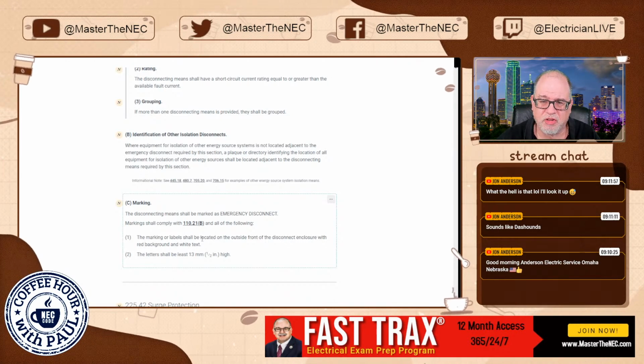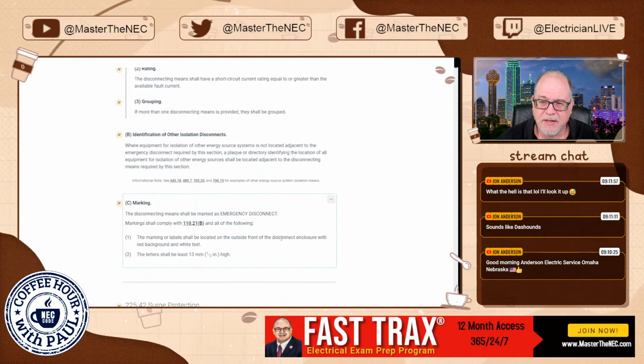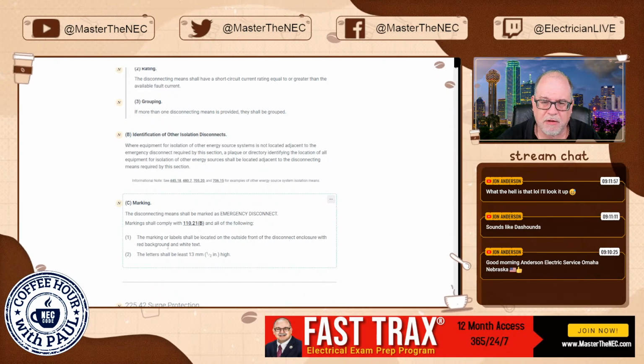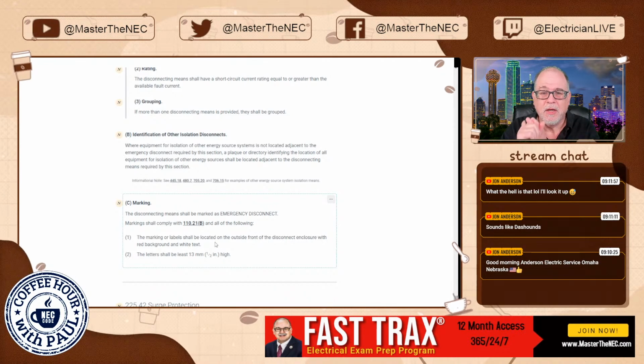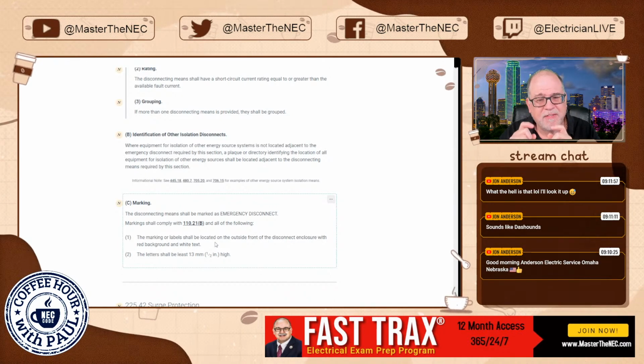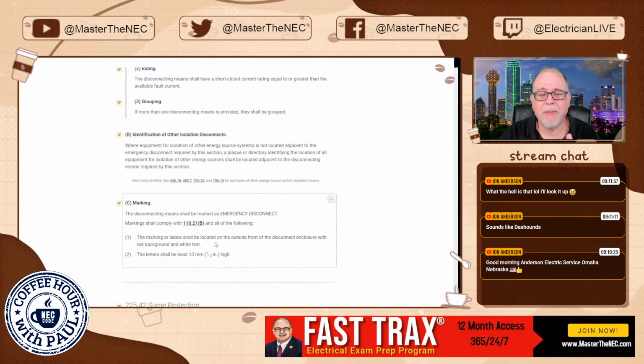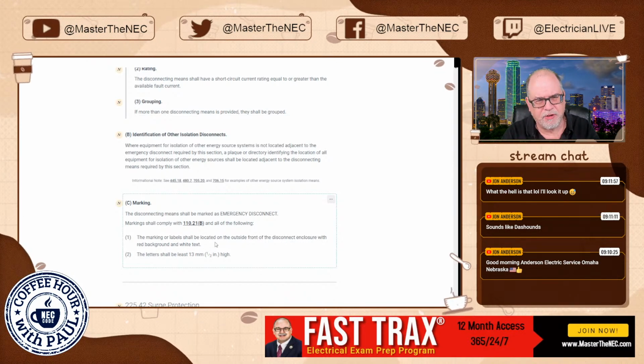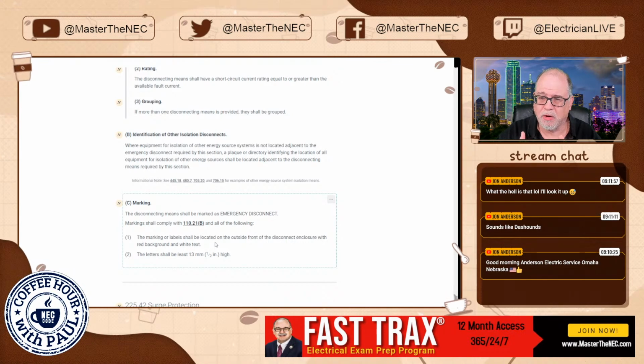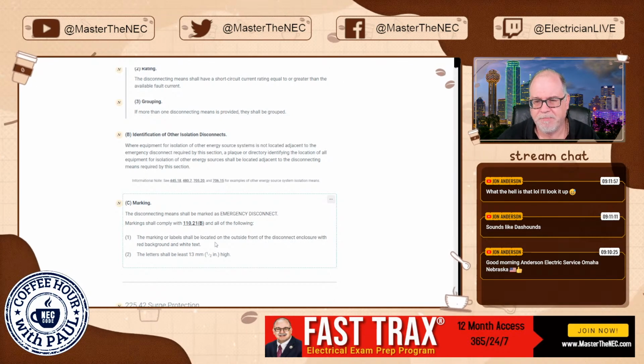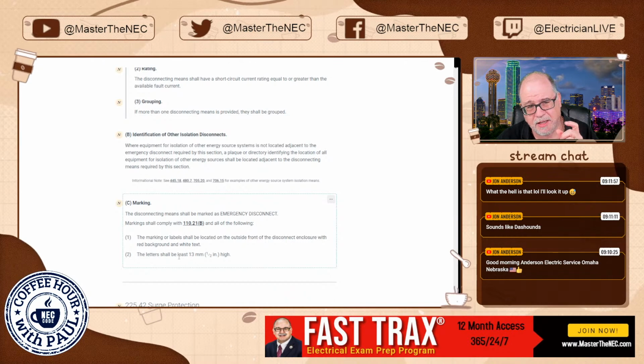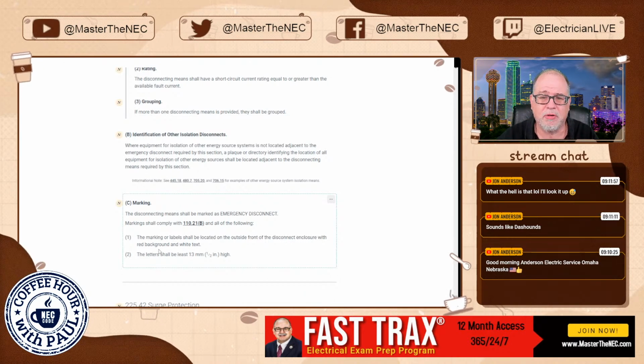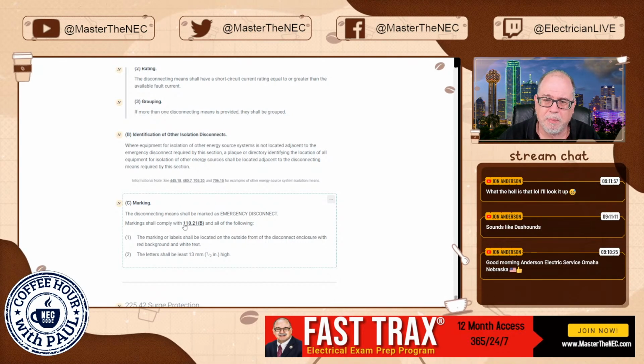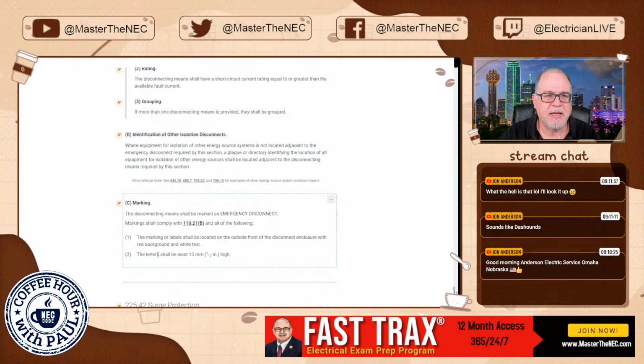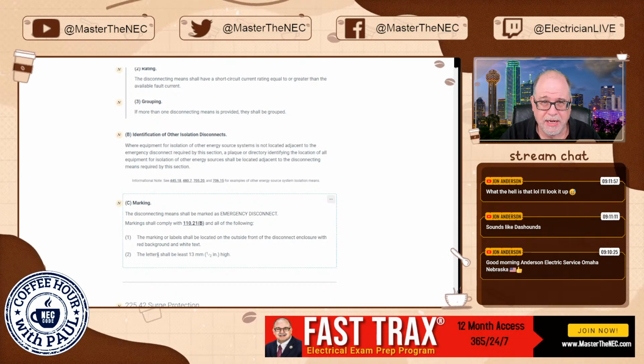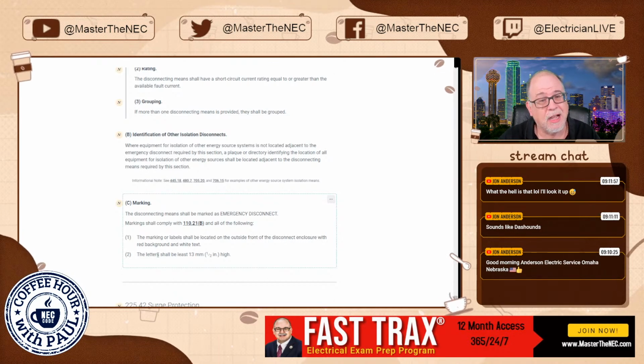It says the marking label shall be located on the outside front of the disconnect enclosure with red background and white text. So the marking is very specific, right? And people have asked through the years, can it be inside of the cover and whatnot? No. It has to be where? On the outside front, all right? And again, it's going to tell you the height of the letters, very specific in these labelings. And also, it goes without saying, they have to comply with 110.21(B), and it means they have to be rated for the environment in which they're located. So no, inkjet labels are not going to work.